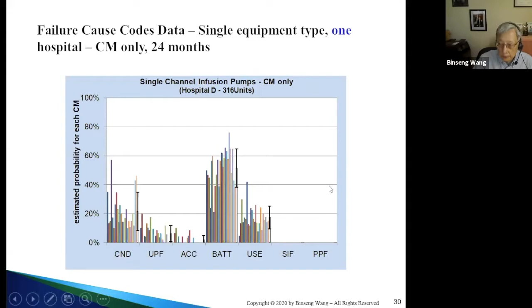Oh, wow, see, in 24 months, the majority of problems are here, batteries. The users are not charging the batteries routinely, and the batteries are dying before the scheduled replacement time. Batteries have to be replaced, yes, but every 2 years or sometimes 3 years even. But if they die within 6 months of replacement, then they have a problem. And that's when we have the data to go back to the users and say, look, you guys are causing problems here. You need to train the users to keep plugging the infusion pump back into the power outlet. And so these are the things that we find.